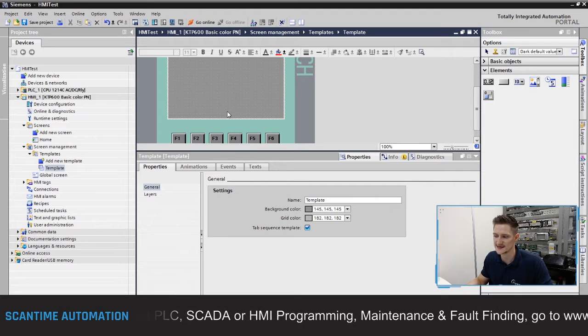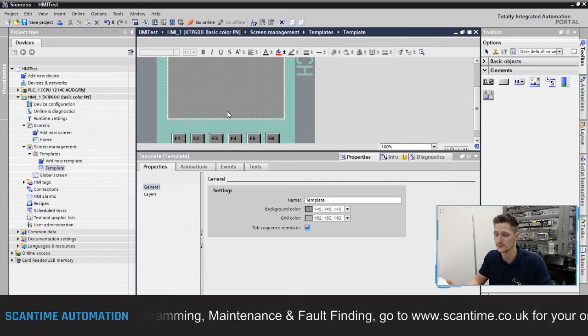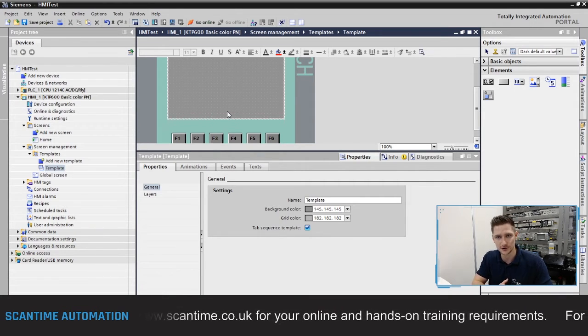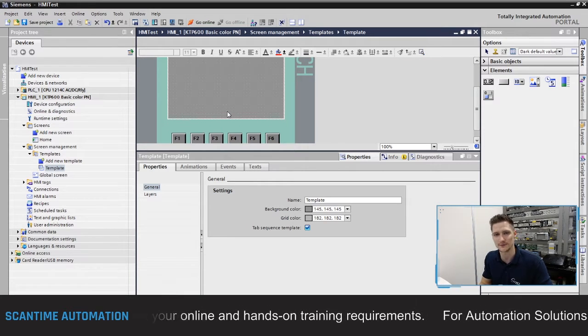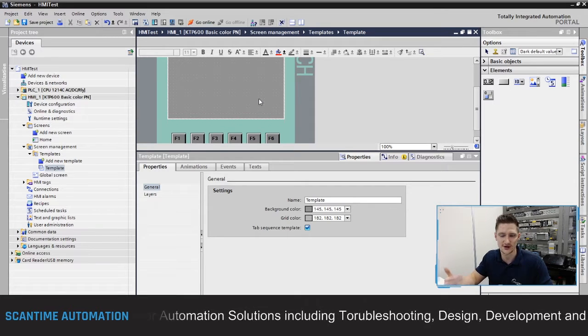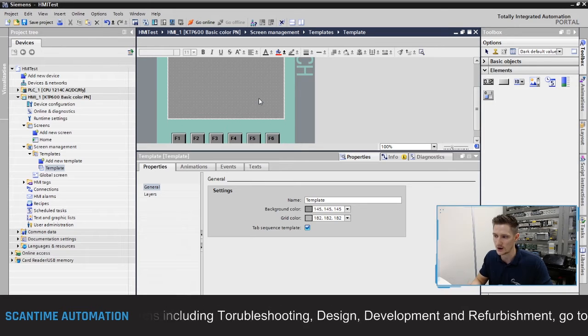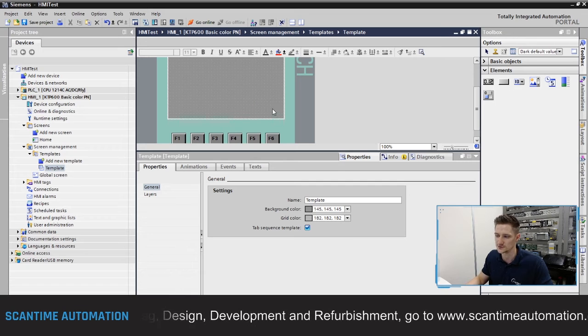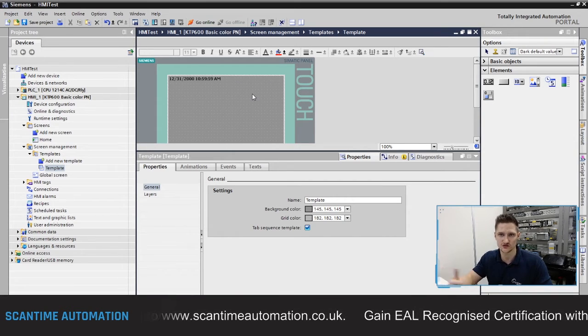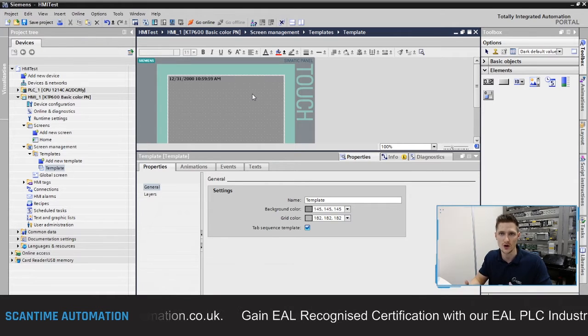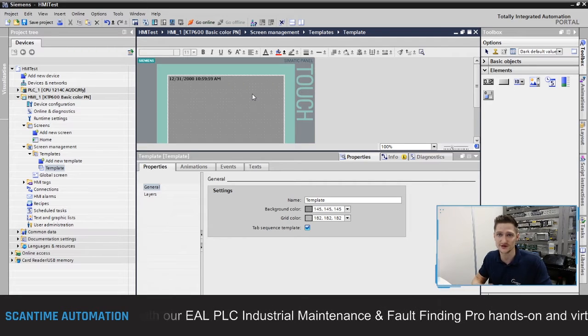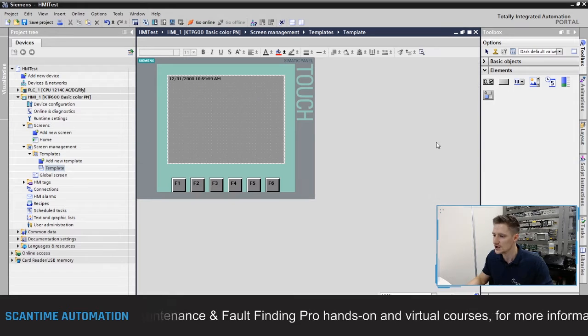We can also add buttons to the template for things like fault resets. One of the most common PLC features is alarms — when an alarm is latched on, the operator needs to reset it via a button, and we could place a fault reset button on the template so it's available on every screen. However, I'm not adding screen titles to the template, because each screen will have a different title — I'll add those on the individual screens themselves.